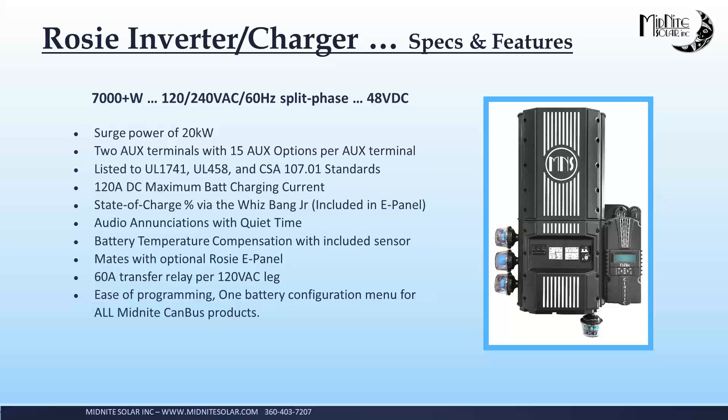The Rosie is 7,000 watts, has a surge power of almost 3x — it'll surge up to about 20 kilowatts. It is 120/240, 60 hertz, split phase out of the box. It is a 48-volt nominal battery-based inverter. You will need a battery that's 48 volts nominal. It runs up to about 65 volt DC on the high end. We actually had a customer the other day with a 60-volt lithium and everything seems to be working well. Some of the cool features of the Rosie: two auxiliary terminals, 15 different auxiliary modes like vent fans, some kinds of diversion, different things like that for opportunity relays. The Rosie also has two-wire generator start built in. The Rosie is listed to UL 1741 and CSA. The mobile Rosie is listed to 1741, 458, and CSA. 120 amps DC maximum charge current.